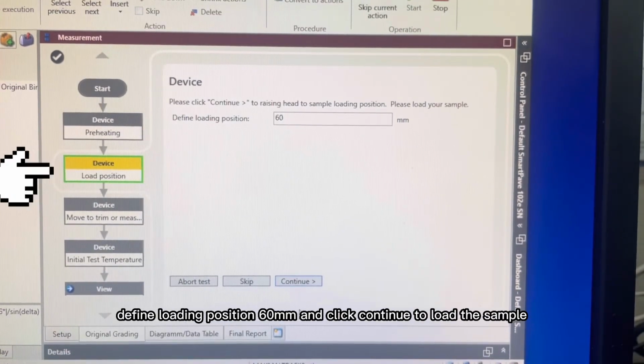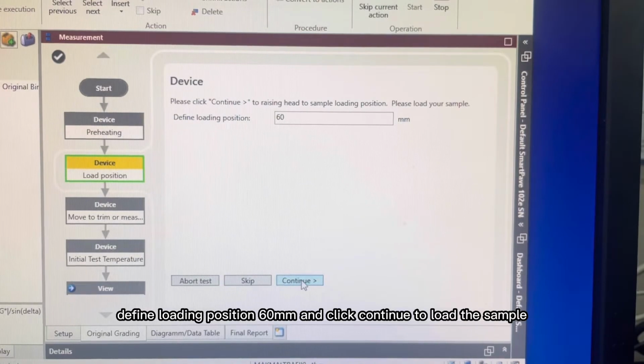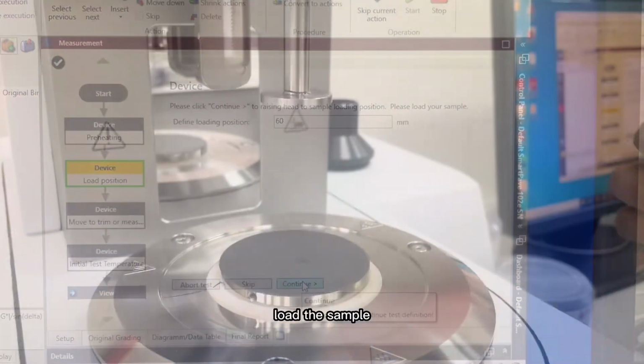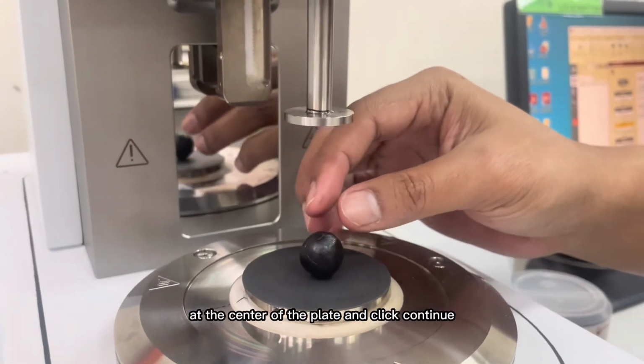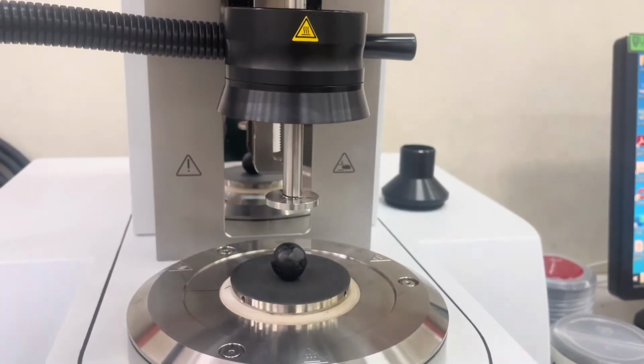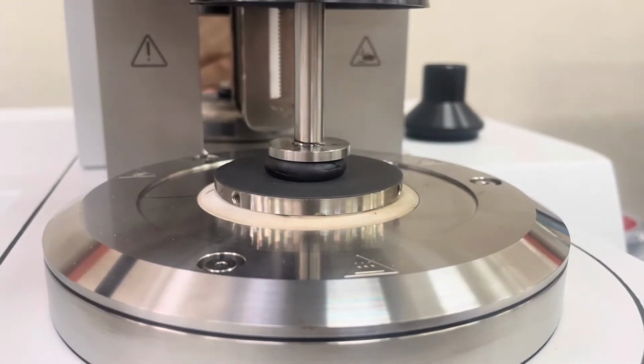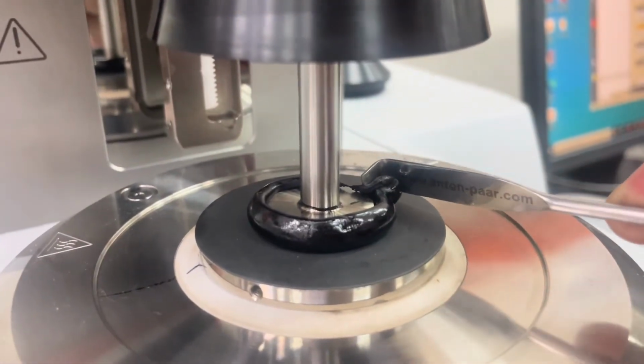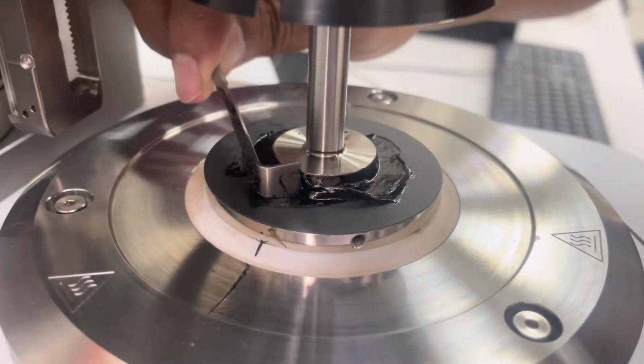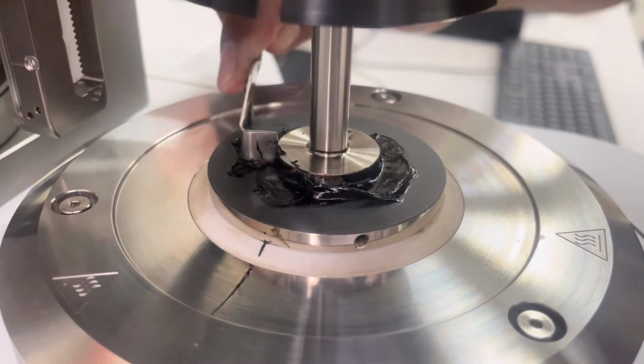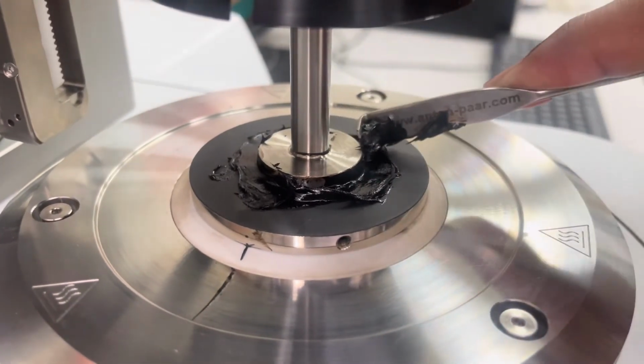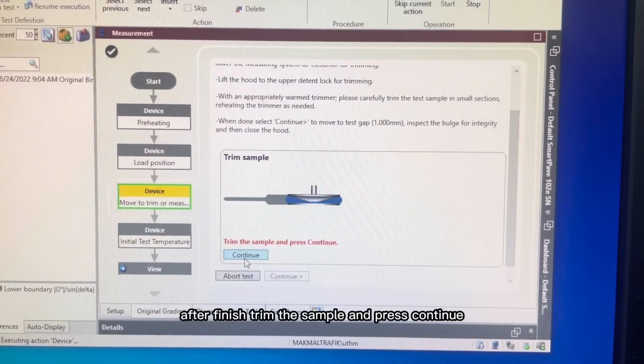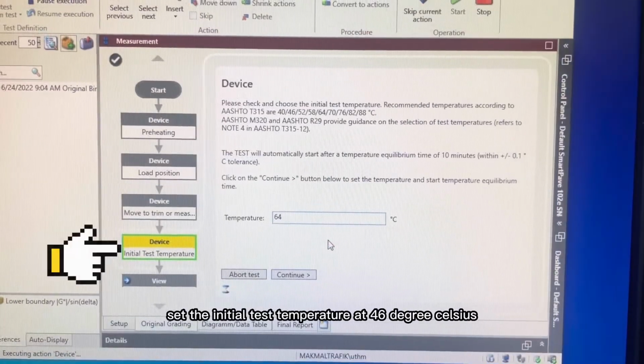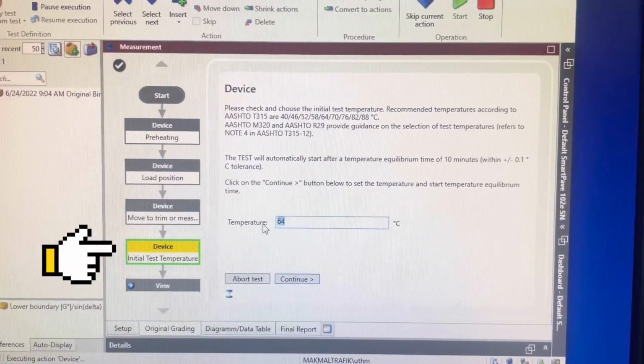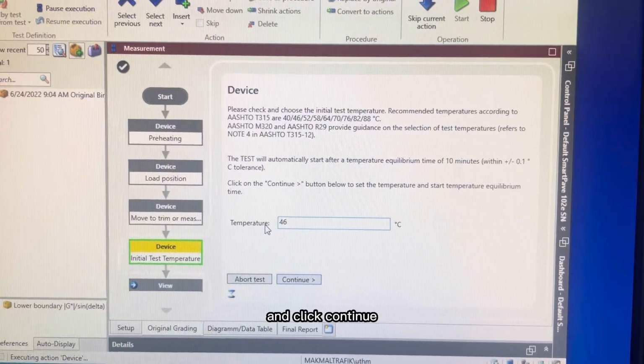Define loading position 60mm and click continue to load the sample. Load the sample at the center of the plate and click continue. Then trim the sample. Finish trimming the sample and press continue. Set the initial test temperature at 46°C and click continue.